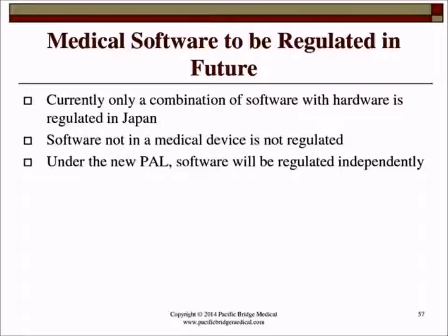Today, software not in a medical device is not regulated. A lot of medical companies are now coming out with standalone software products that could be used in a variety of CT machines or a variety of other products. Under the new PAL, independent software will be regulated independently, so the software can be registered as a standalone product. Again, standalone diagnostic software will need to apply for pre-market product approval depending on the product's risk. And again, you have either notification, certification, or approval from the PMDA.